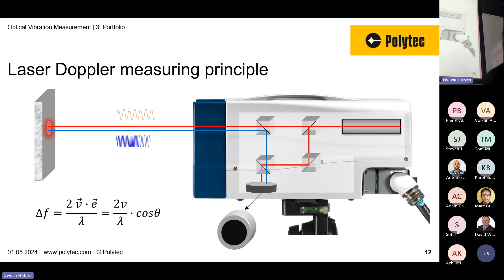Now a little bit about our portfolio and some of the instruments we have. We have two main types of equipment in our portfolio. The first category is single point, and as you can see, this is one of our single point portable vibrometers. Single point means just one laser light from the sensor, and if you want to do multiple measurements, you need to physically move the laser to the specimen or object you want to measure.